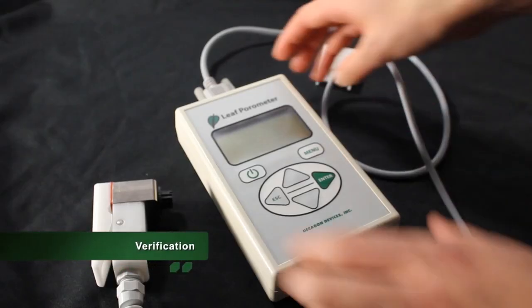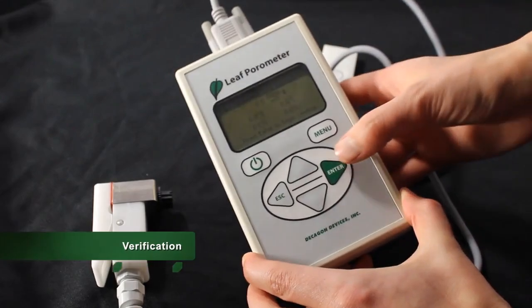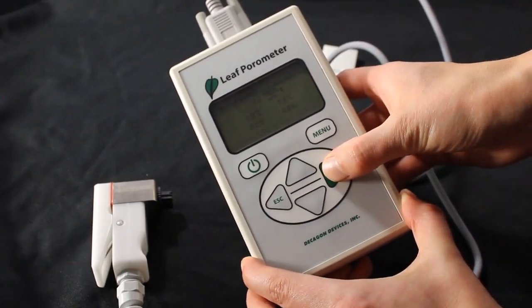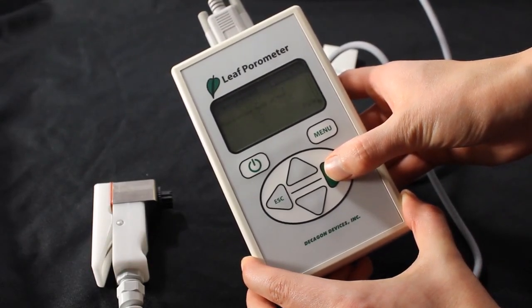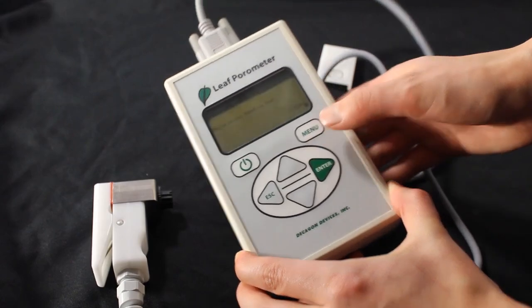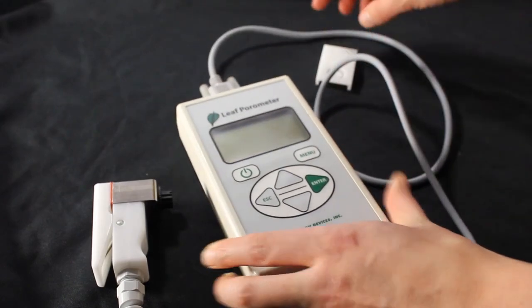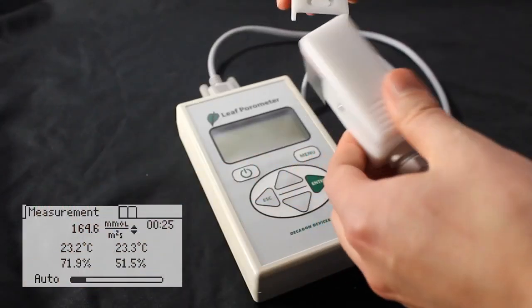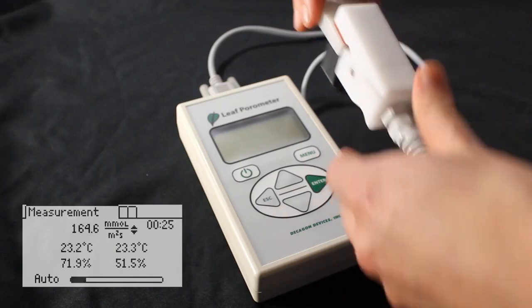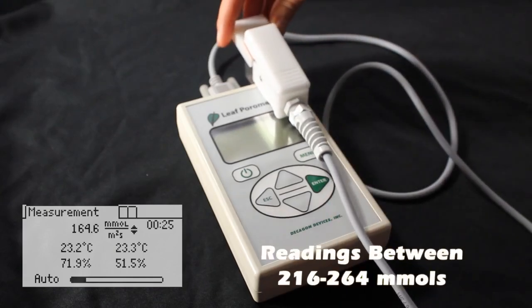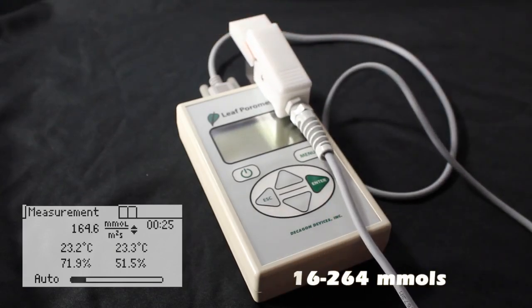At this point, it is a good idea to take a couple of verification readings to ensure the porometer is reading correctly. Immediately after the calibration is saved, verify the reading. Go to the measurement menu on the screen and press Enter to take a reading. Clamp the sensor head over the calibration plate. The reading should be between 216 to 264 millimoles per meter squared per second.